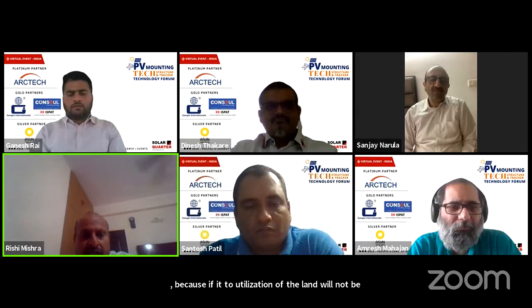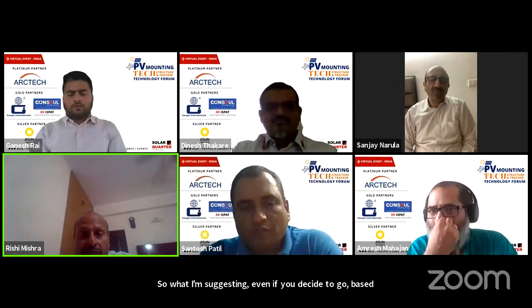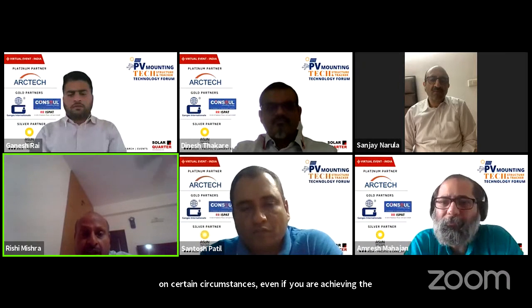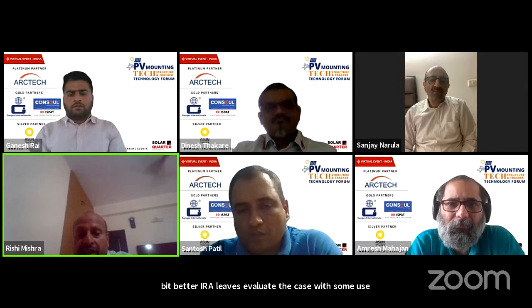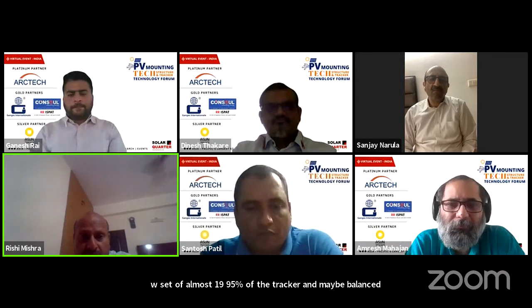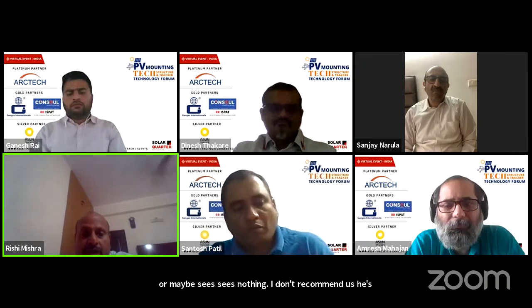So what I am suggesting, even if you decide to go based on certain circumstances, even if you are achieving a better IRR, please evaluate the case with usage of almost 90-95% of the tracker, and maybe balance 5% of the fixed tilt structure, or maybe seasonal tilt. I don't recommend a seasonal tilt, but I will recommend the fixed tilt structure.